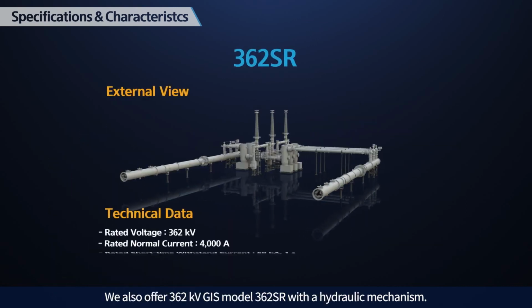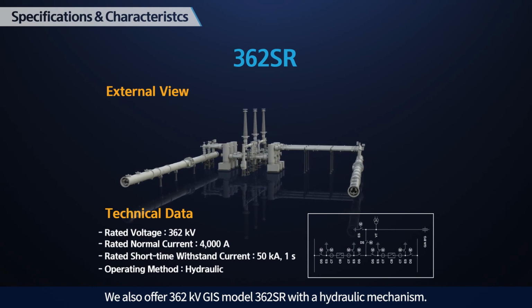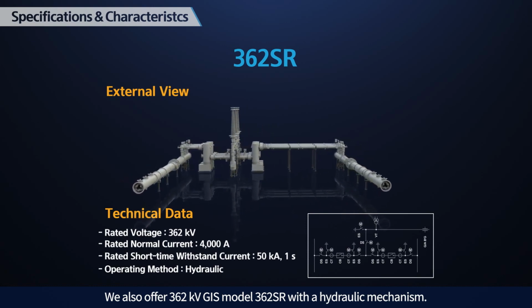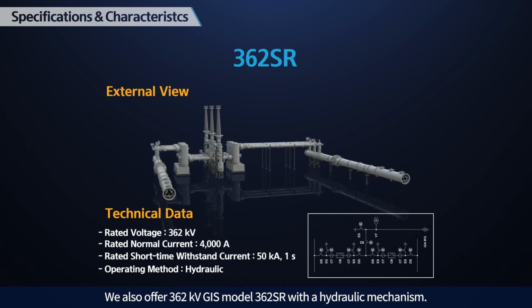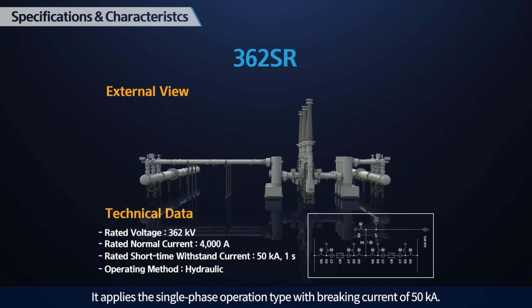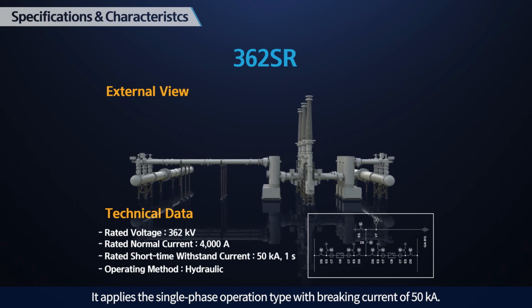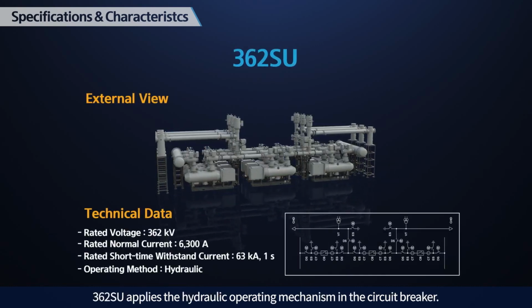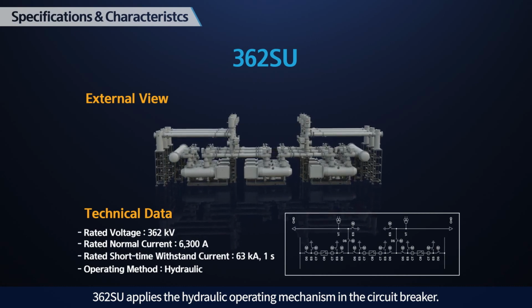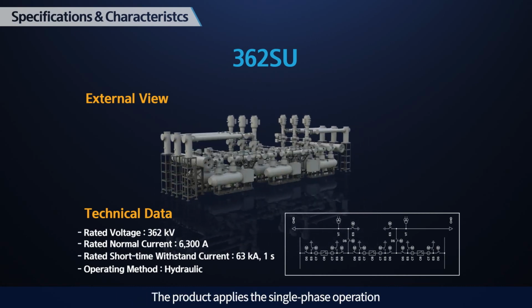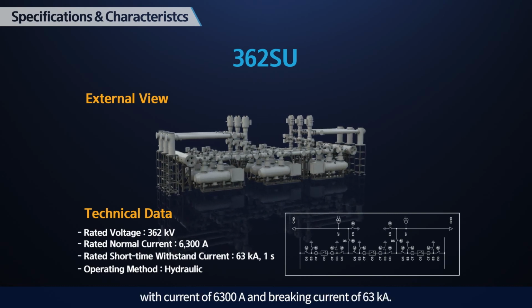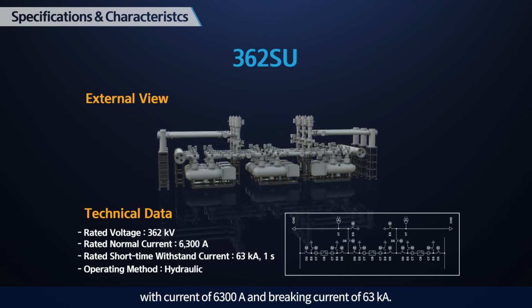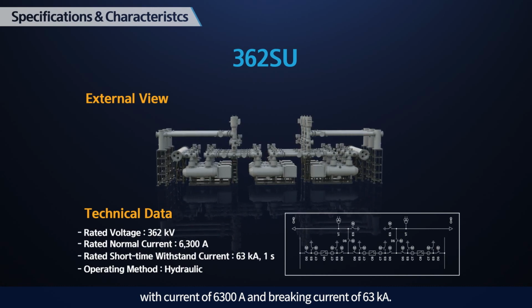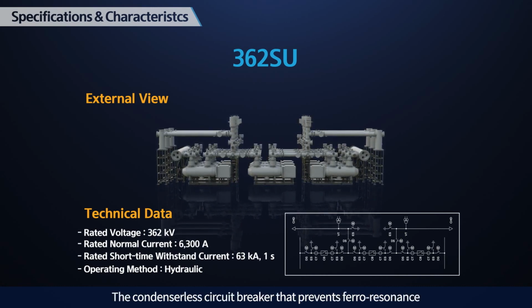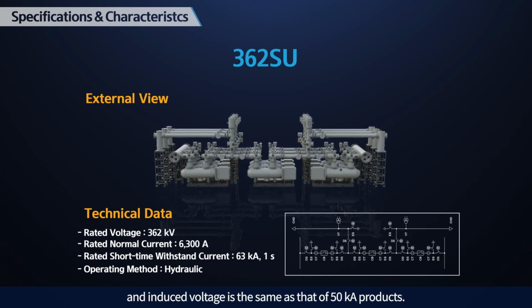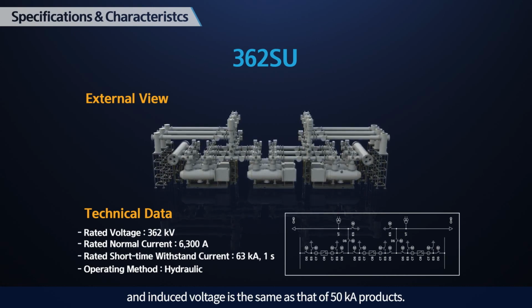We also offer 362 kV GIS model 362SR with a hydraulic mechanism. It applies the single-phase operation type with a breaking current of 50 kA. 362SU applies the hydraulic operating mechanism in the circuit breaker. The product applies the single-phase operation with a current of 6,300 amperes and breaking current of 63 kA. The condenserless circuit breaker that prevents ferroresonance and induced voltage is the same as that of 50 kA products.